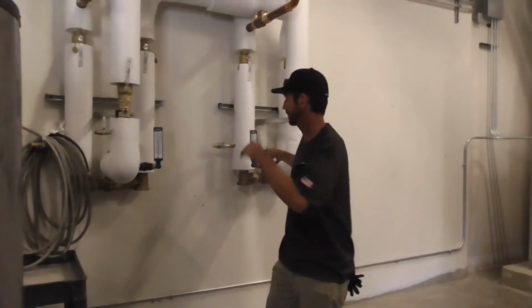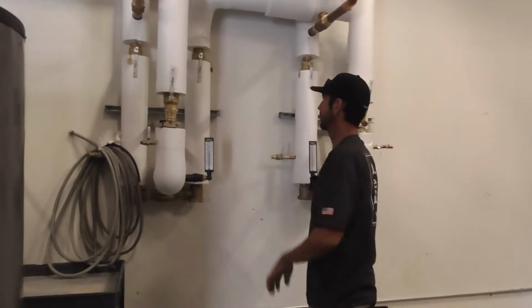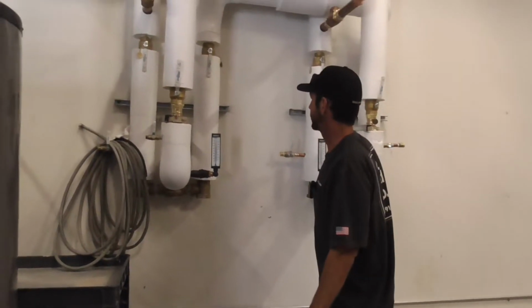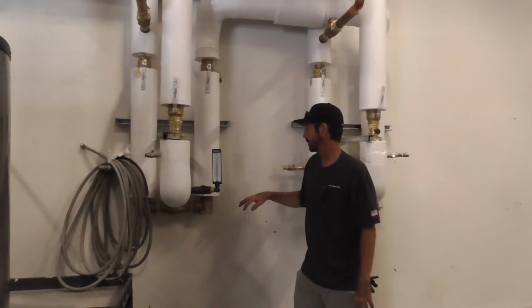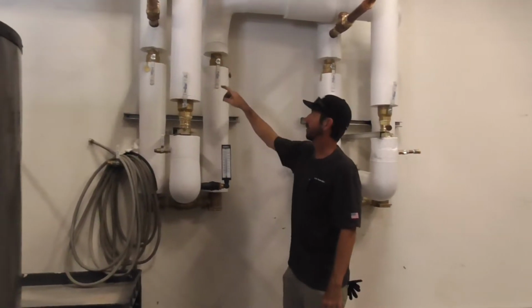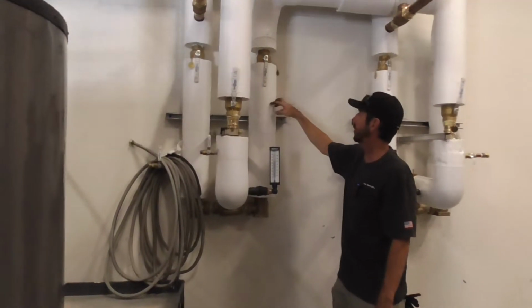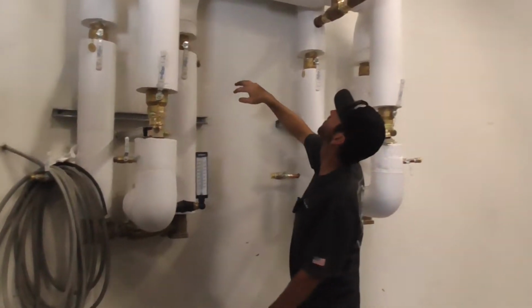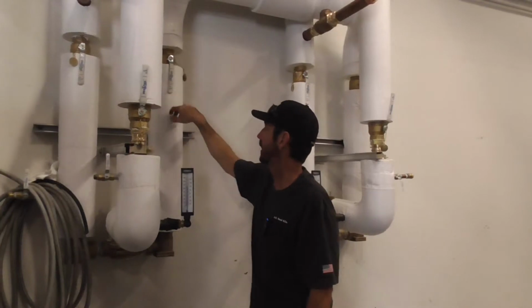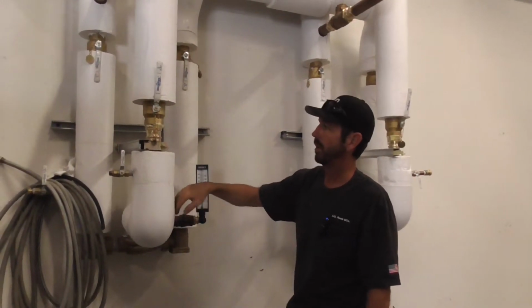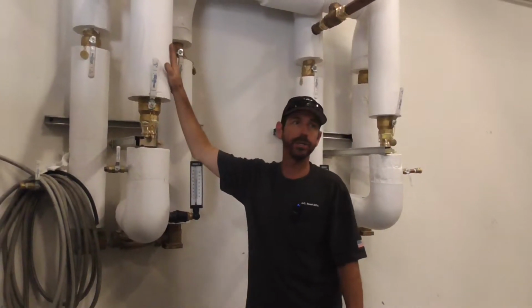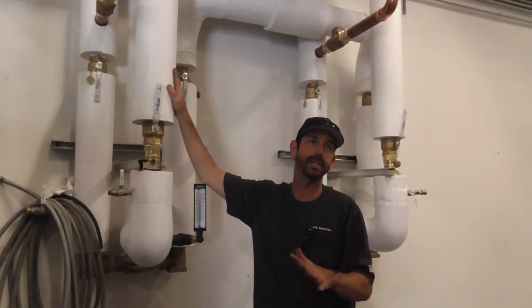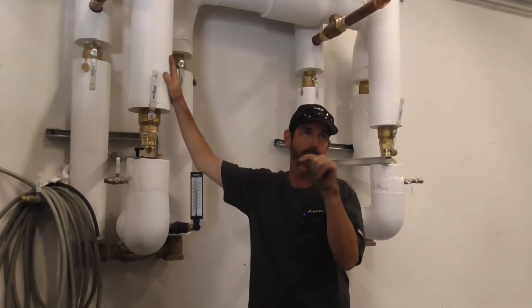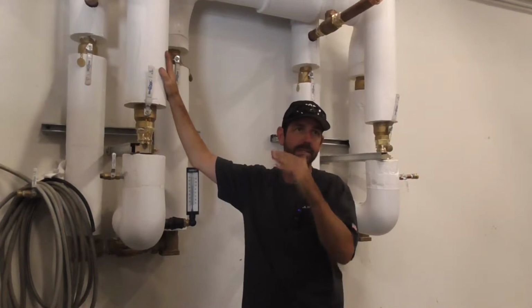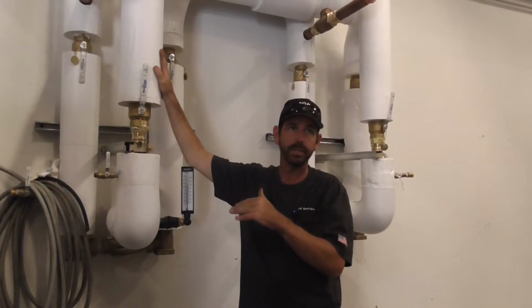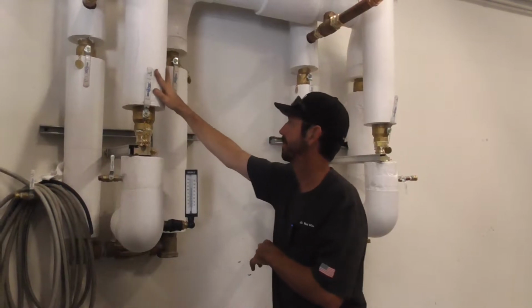So moving on over here, our domestic water comes out and it goes through our mixing valves over here. And we have our cold water as well. Cold's going to be on this side over here, hot's on this side. And then our mixed water outlet right here, 120 degrees. It's like 118, okay? I always try to shoot like a couple degrees below your set point in case the mixing valve overshoots a little bit. Just a couple, so they're set for 118, okay?